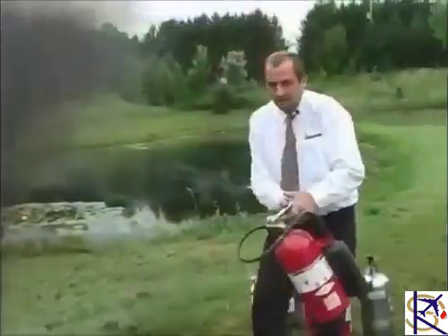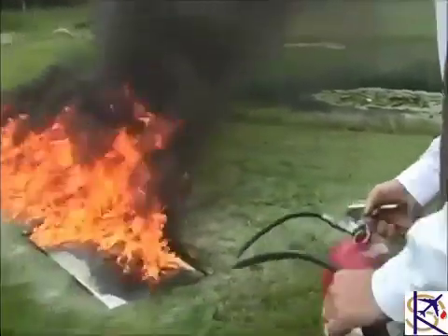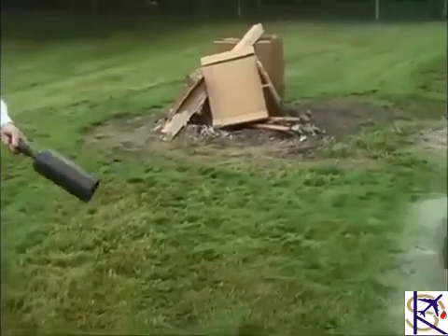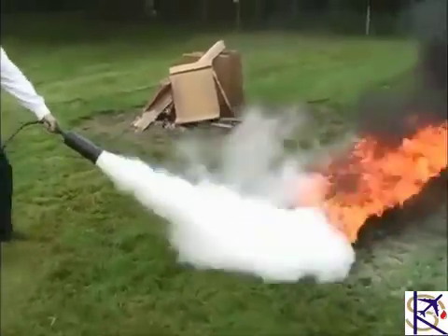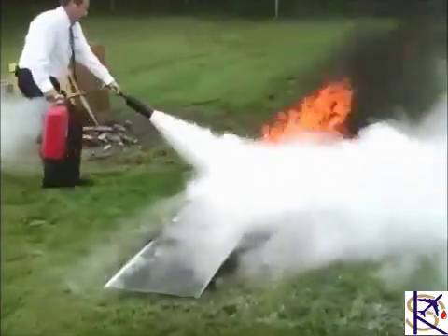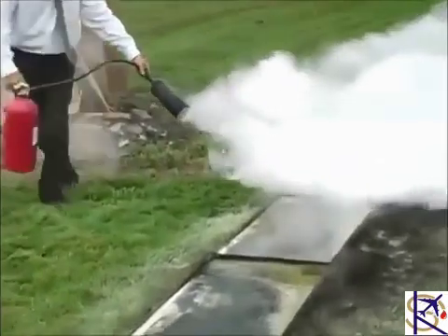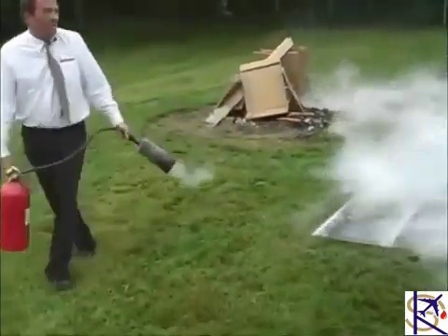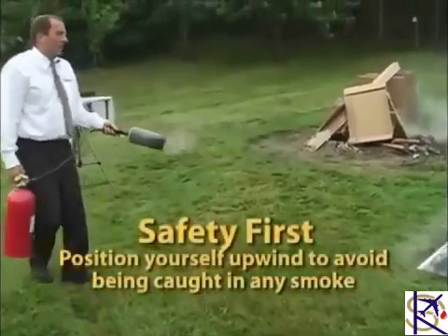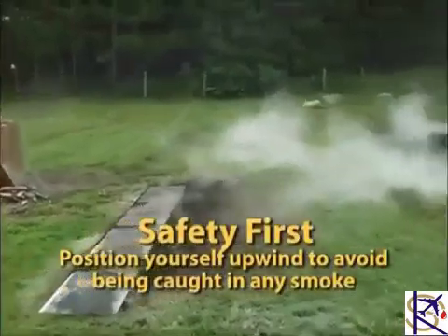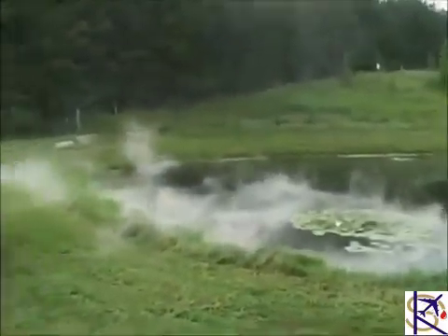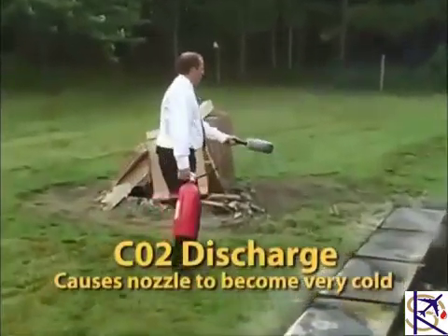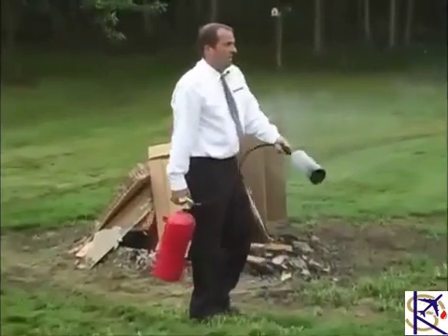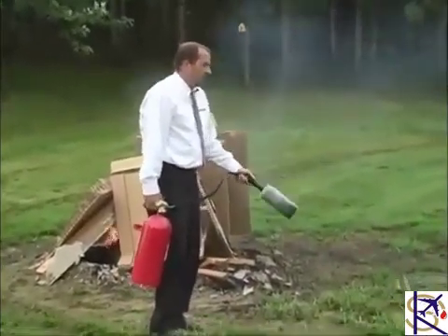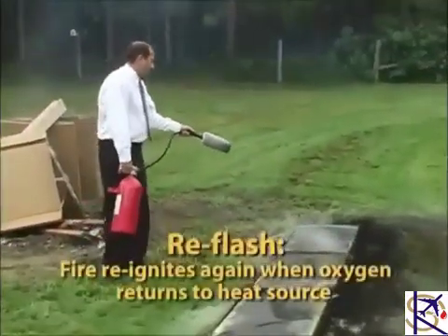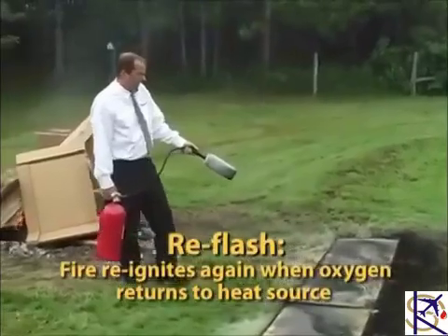This is a 10-pound CO2, pulling the pin. Positioning the nozzle. Position yourself upwind so that the smoke and flames don't come towards you. Notice, the nozzle is cold, discharging CO2. The windier it is, the harder it is for it to put the fire out. Basically, it removes the oxygen. Be very careful that it does not reflash as soon as the oxygen hits it again.